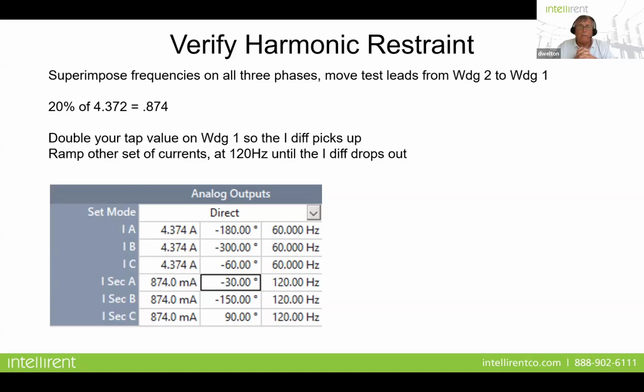Okay, so how do we verify our 20% harmonic? Now this is kind of tricky because we have to do 1 winding at a time. What we do is we superimpose frequencies on all 3 phases. So we're going to move our 3-phase test leads from winding 2 to winding 1. We're going to leave the actual ones, so now we've got 2 sets of test leads going to winding 1. So if it's set at 20%, we're going to look at our second harmonic. A second harmonic would mean that we're going to have in this test lead 120 hertz. Fourth would be 240. Okay, so a second harmonic component is 120 hertz. So we set this set of test leads to 120 hertz, and we start to ramp it up.